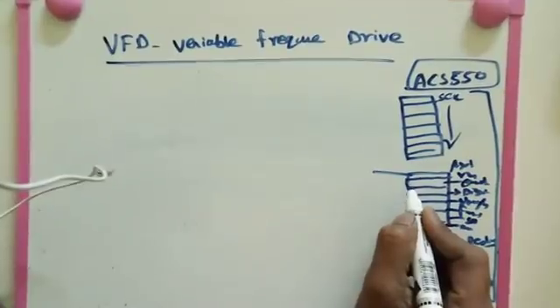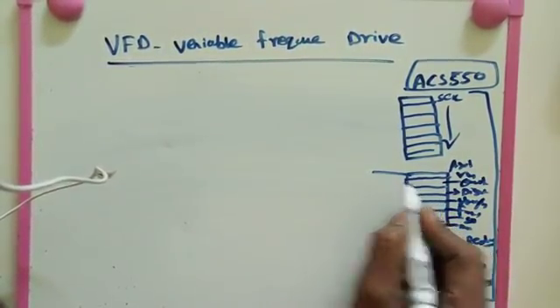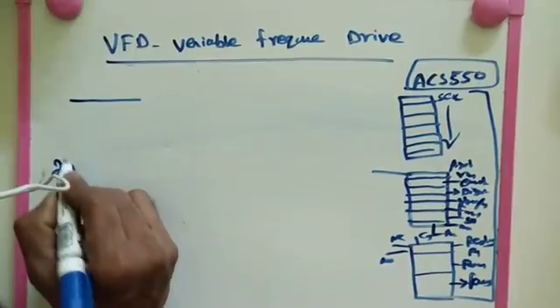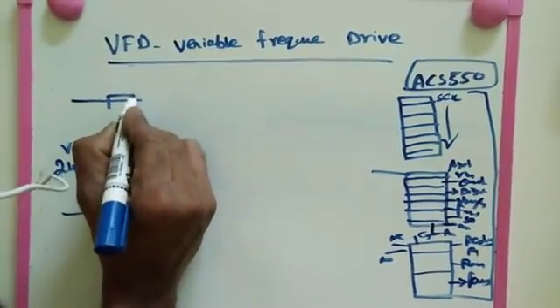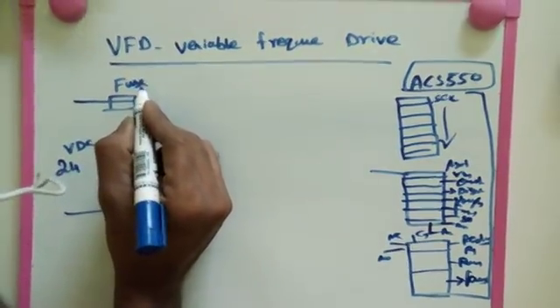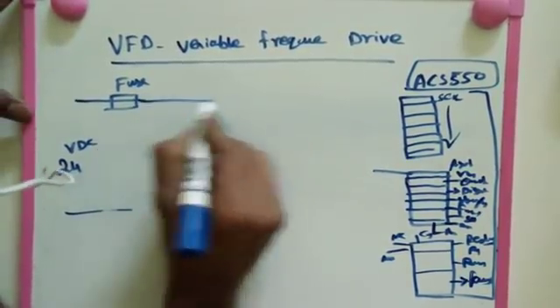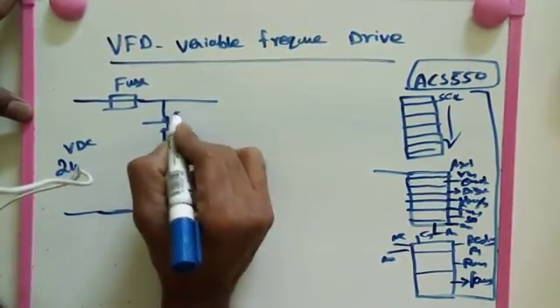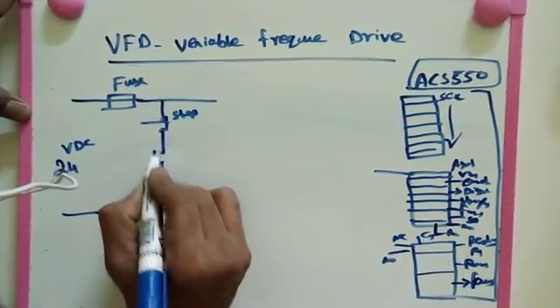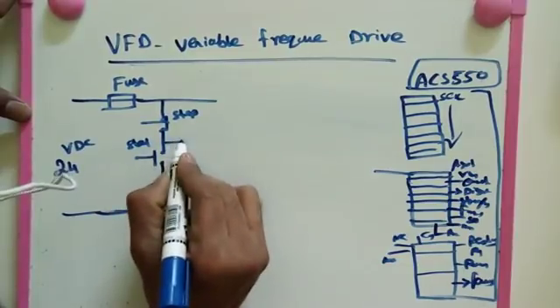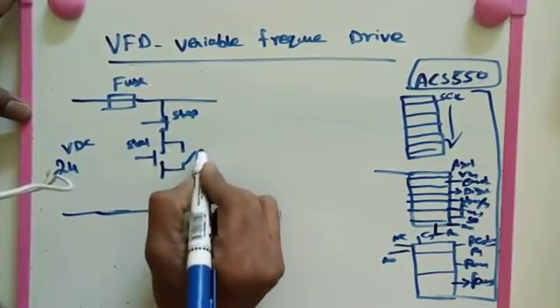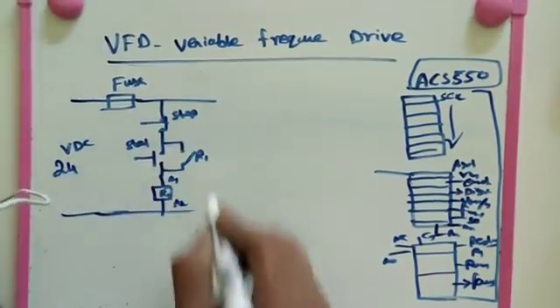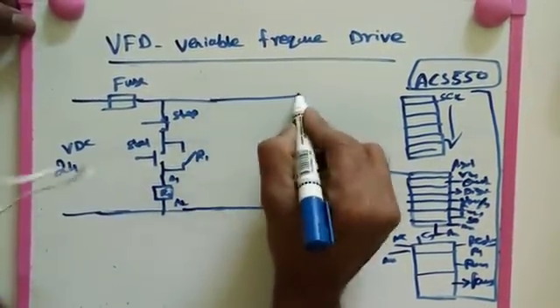Now I will draw the control diagram. We use 24 volt DC as the source supply, with a fuse after it. Then we make start and stop control using relays — a stop push button, a start push button, and NO contact of relay R1, connecting to relay coil R1 on terminals A1 and A2. This is a simple start-stop circuit to control the VFD.